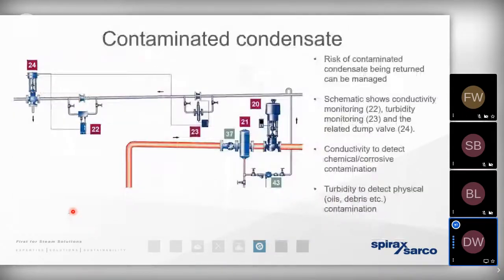But we also know that certain processes are knowingly dumping the condensate to waste. And that could be through fear of the condensate becoming contaminated with oils, fats, acids. Because if we brought that contamination back to the boiler, then that could be quite a costly failure for the boiler itself. But it could also mean that we're potentially cross-contaminating other processes. We could have contaminated steam going out to other areas of site. So quite often, sites are knowingly dumping that condensate to waste.